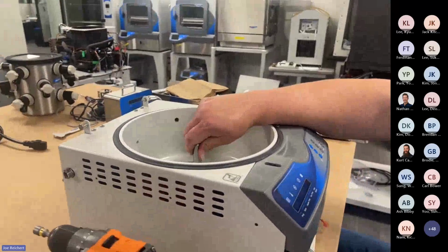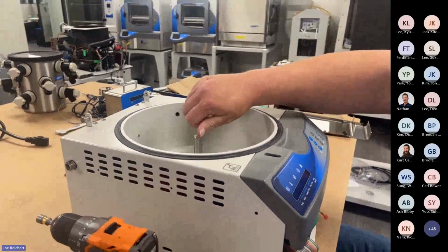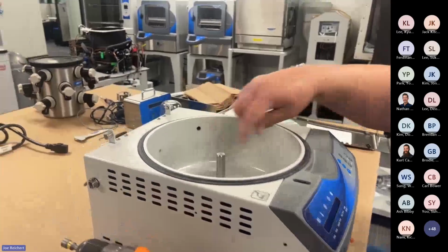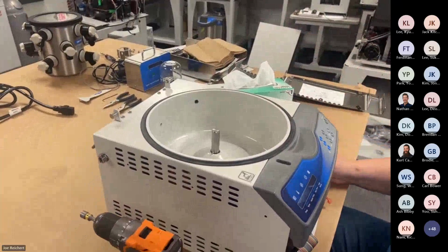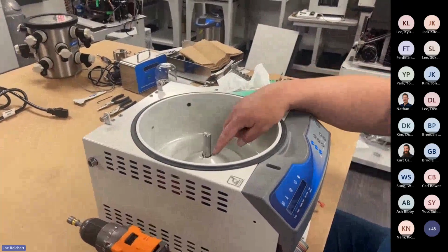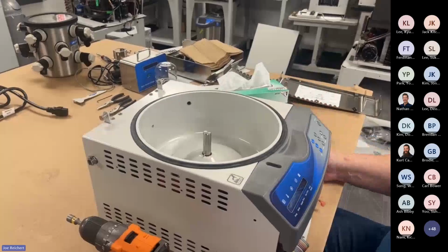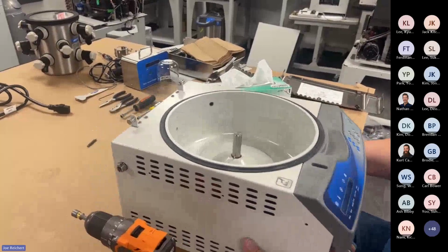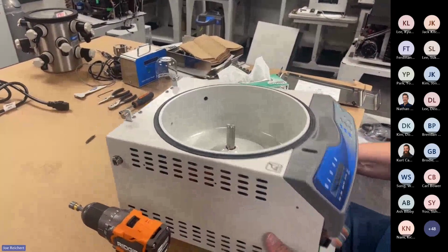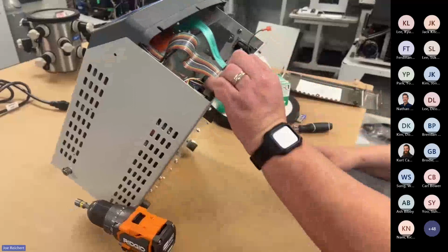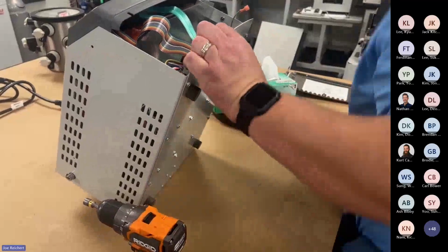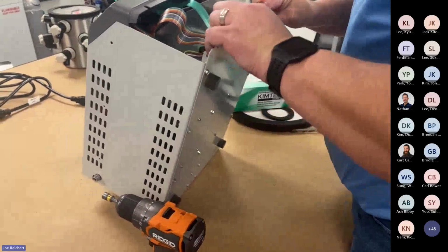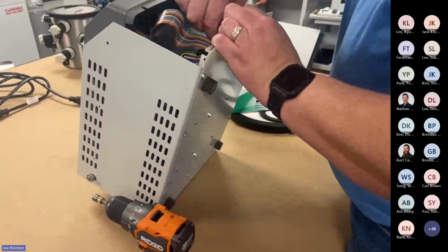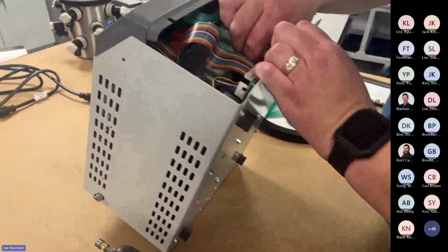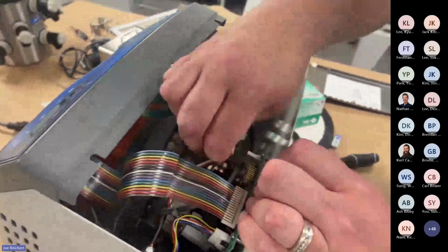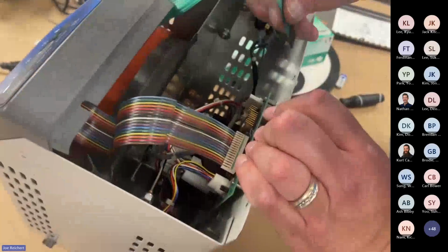It might even have glass in the bearing. But this is not spinning at the proper RPMs, and that's why it's throwing motor error. So it can either be from the bearings or the Hall effect sensor itself. On a refrigerated unit, if you get condensation underneath the chamber, you can get that getting into that sensor. We now coat it with RTV to keep it more waterproof.